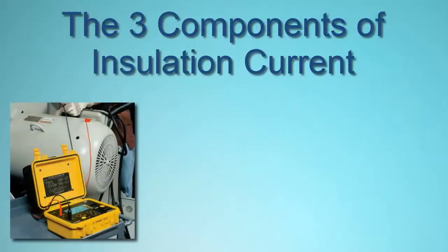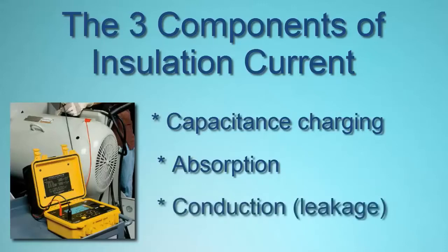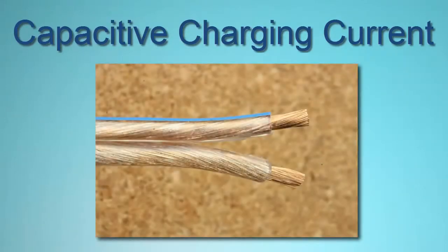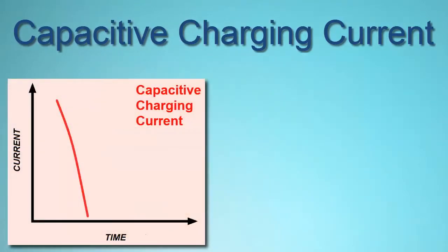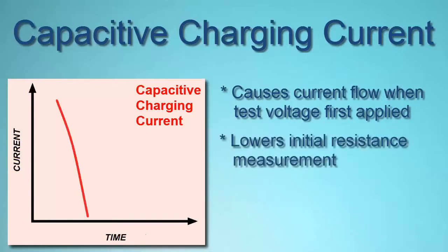To properly interpret test results, it's important to understand that the total current flowing through the insulation consists of three components: capacitive charging current, absorption current, and conduction or leakage current. When two conductors are in close proximity separated by an insulator, they can act as a capacitor. When test voltage is first applied, this capacitive charging effect results in current briefly flowing through the conductors until the voltage across the insulation reaches the test voltage. Consequently, the initial resistance measurement will be relatively low and then quickly rise as the capacitance becomes fully charged.